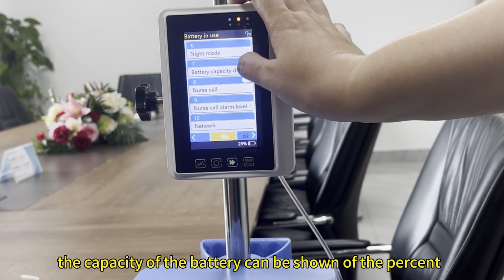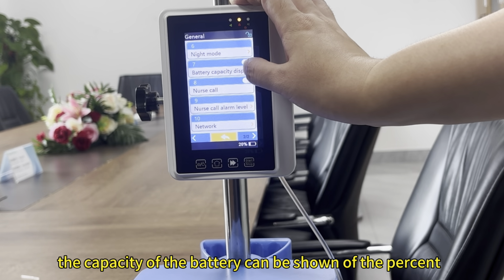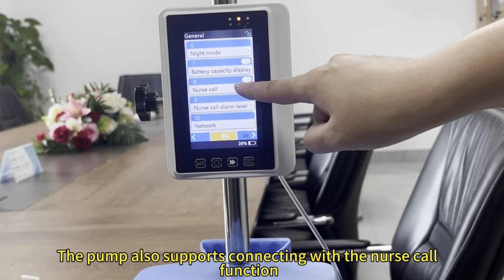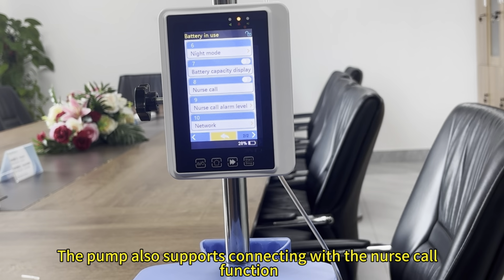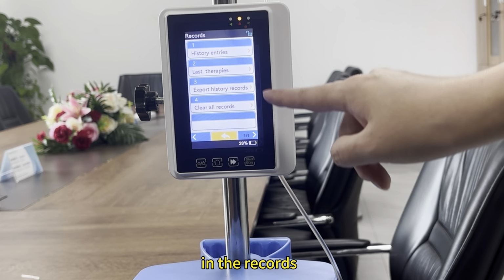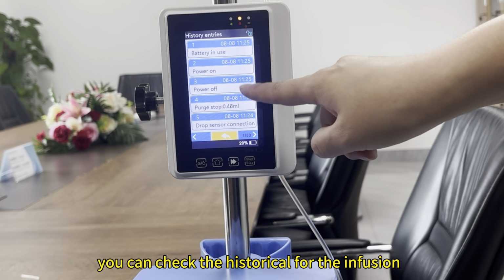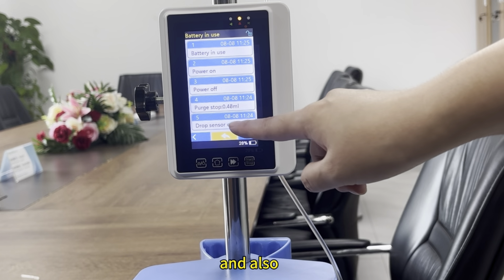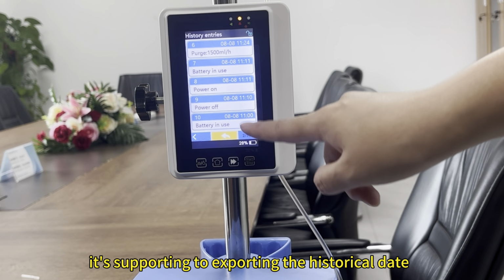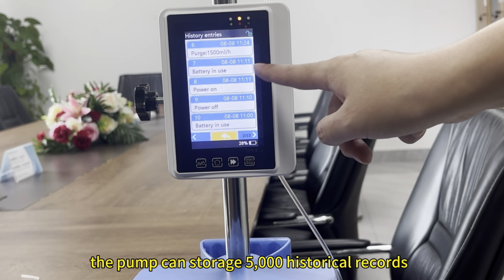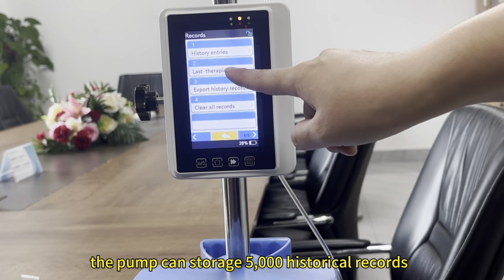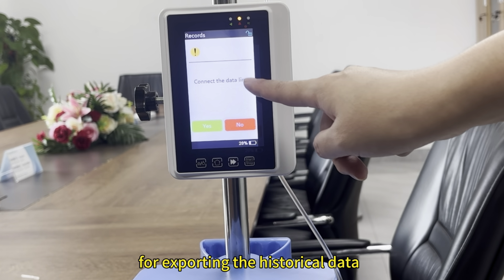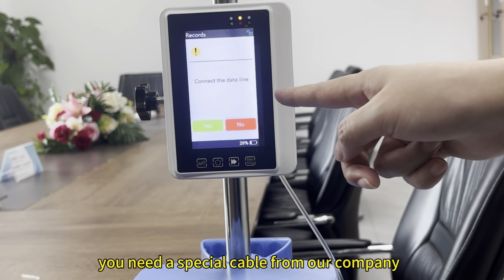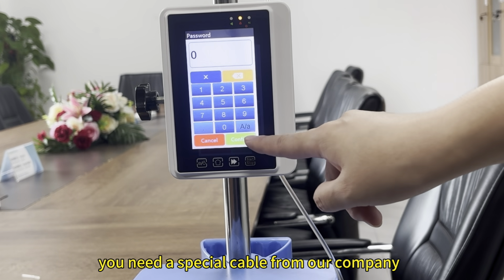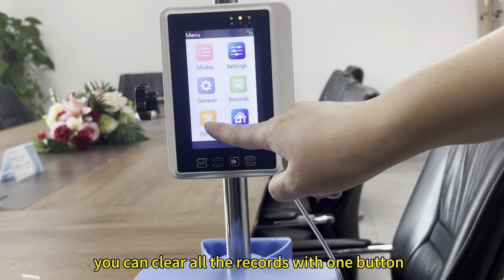The capacity of the battery can be shown as a percent of the rest time. The pump also supports connecting with the nurse call function. In the records, you can check the history of the infusion. And it also supports exporting the historical data from the pump. The pump can store 5,000 historical records. For exporting the historical data, you need a special cable from our company. You can clear all the records with one button.